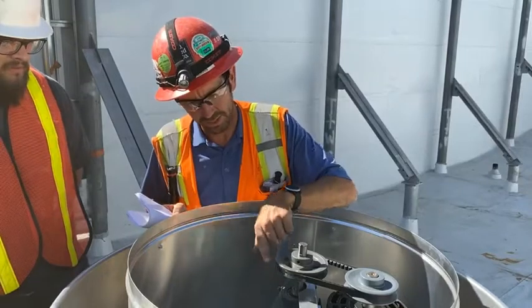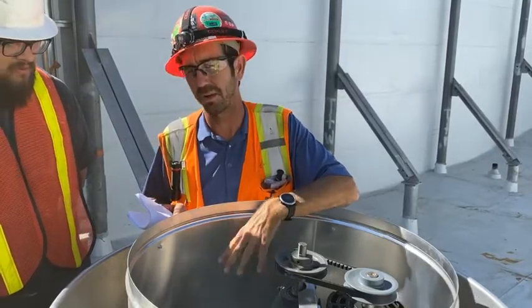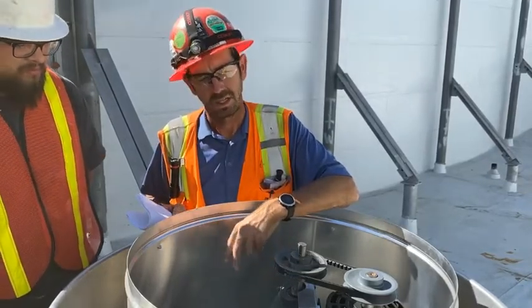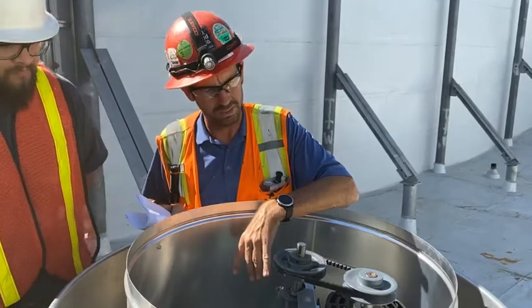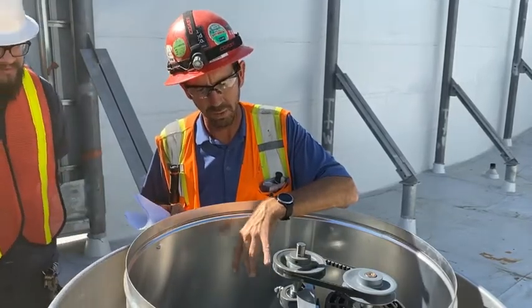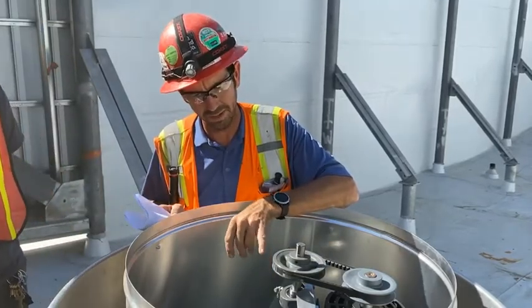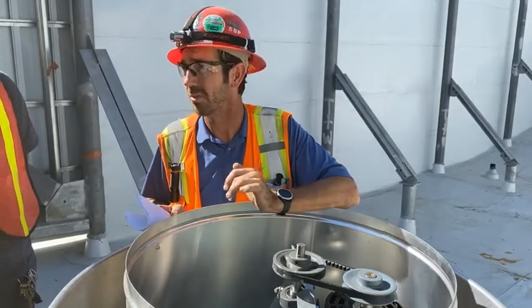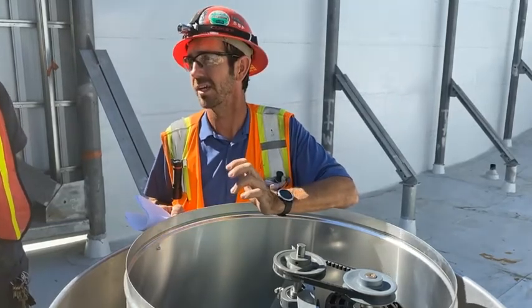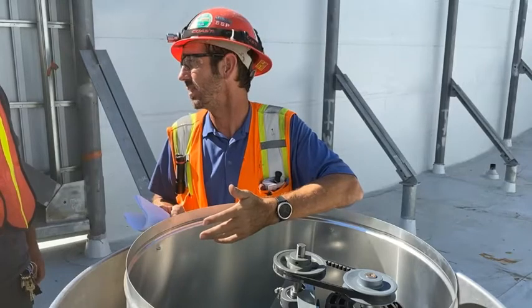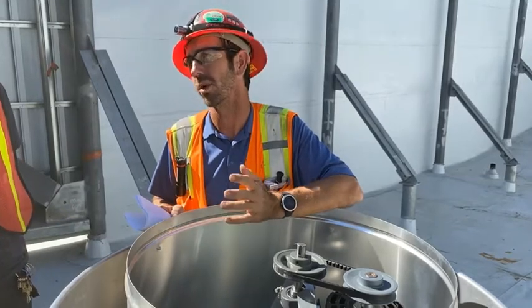So we'll want to grease the bearings. These fans aren't going to be running all the time. So I would say we'd want to grease the bearings probably quarterly, with no more than a couple squirts. But obviously, it's going to depend on the grease gun you guys use. Some grease guns distribute more grease than others, okay?